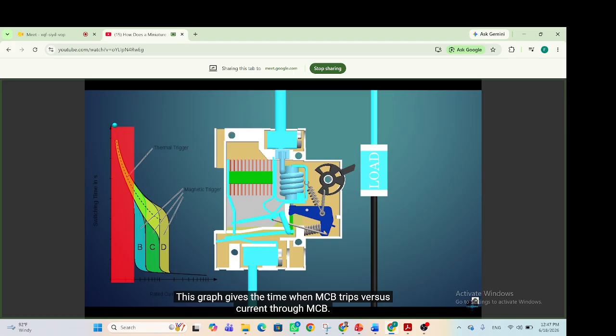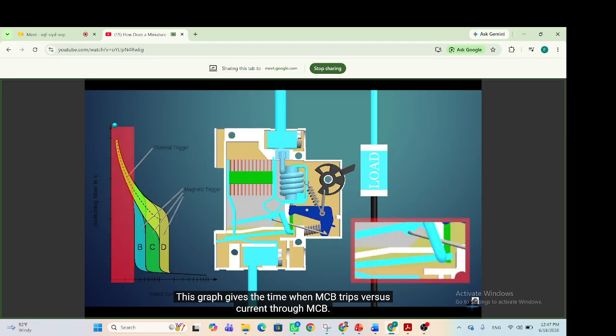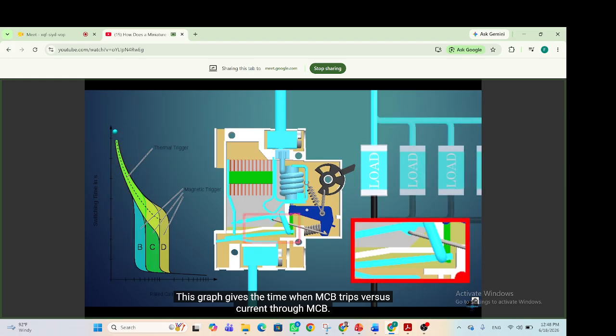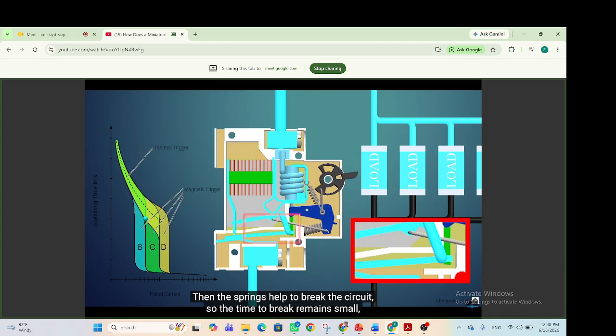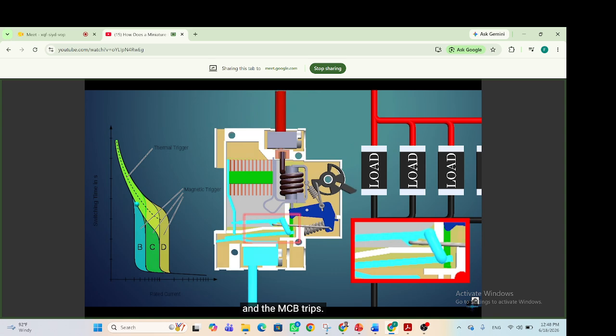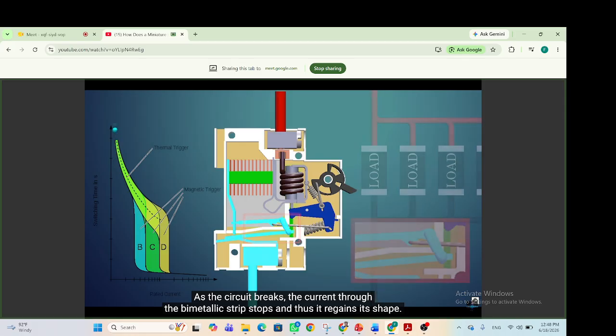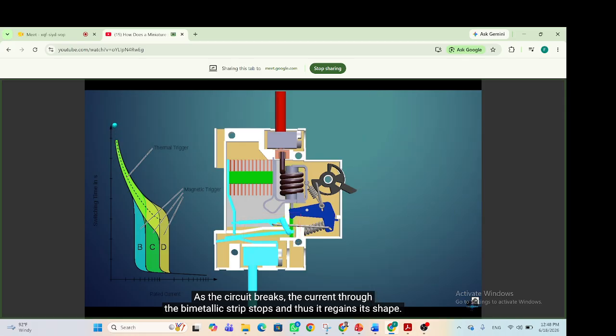This graph gives the time when the MCB trips versus the current through it. As the current increases, the bimetallic strip bends. The strip then pulls a small plastic part, and this moves the mechanism. Then the springs help to break the circuit, so the time to break remains small, and the MCB trips. As the circuit breaks, the current through the bimetallic strip stops, and it regains its shape.